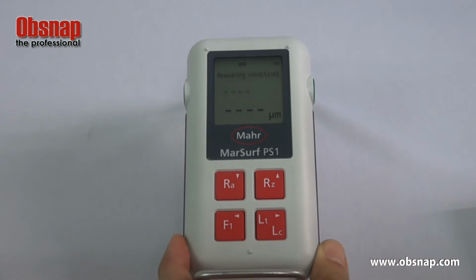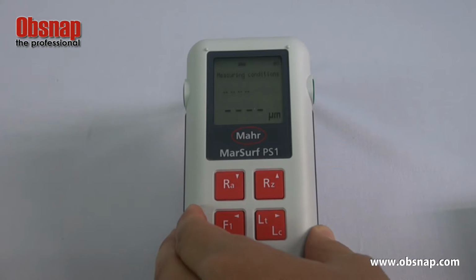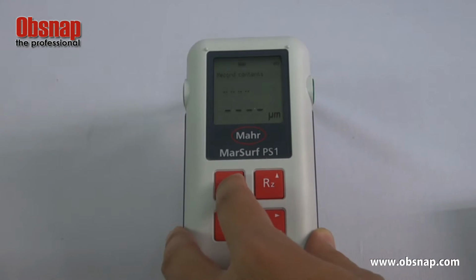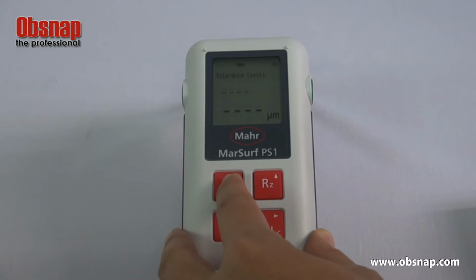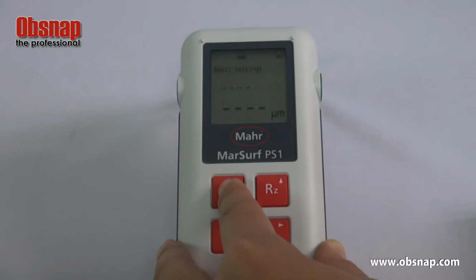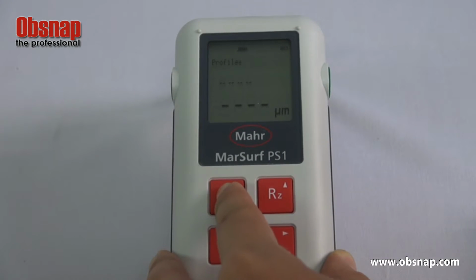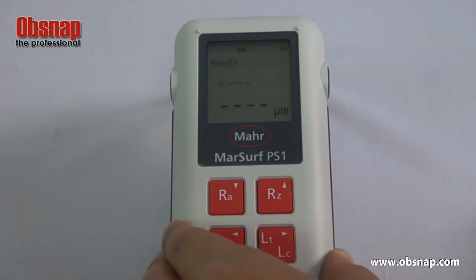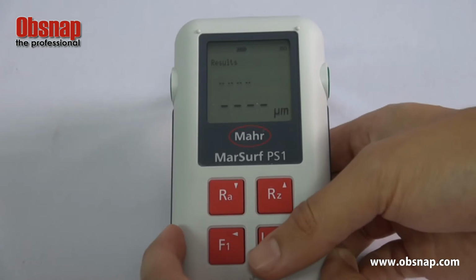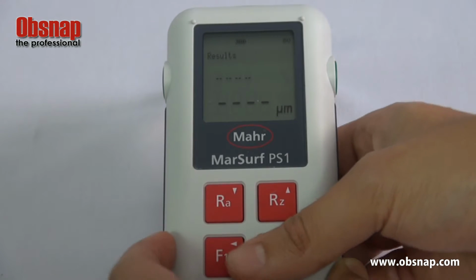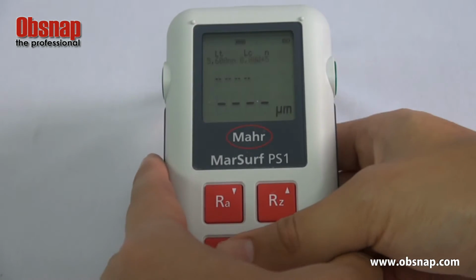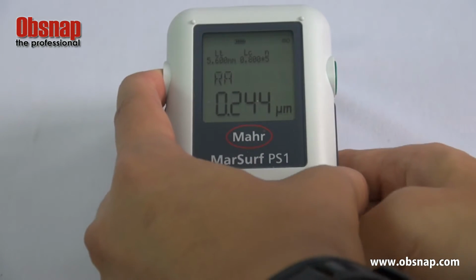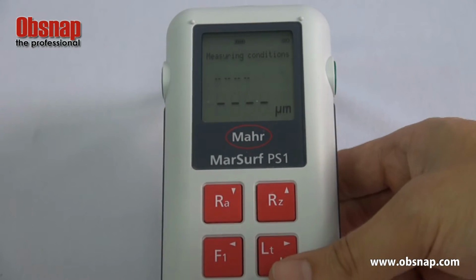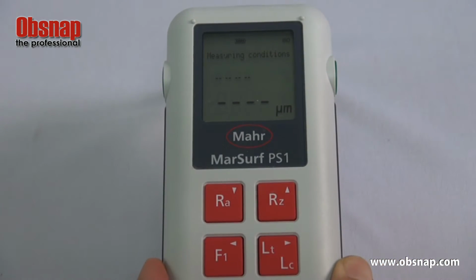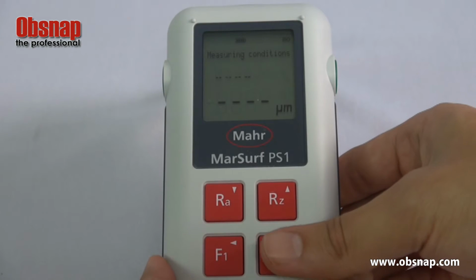So this is the menu. The first thing in the menu is measuring condition. Next are record contents, tolerance limits, basic setting, profile, and result. Inside this menu, each of them has a sub-menu. So I go in again, LT, LC, and the green button together. Okay, first, the measuring condition. This is where you set the measuring condition.